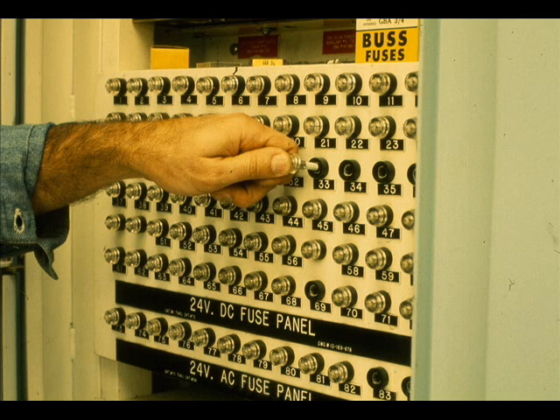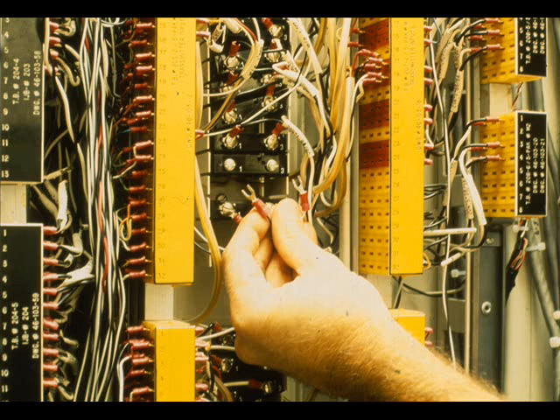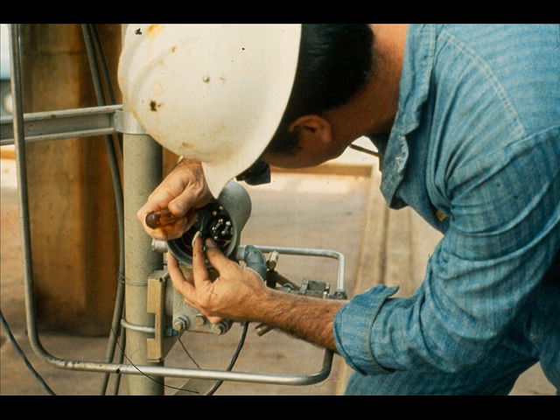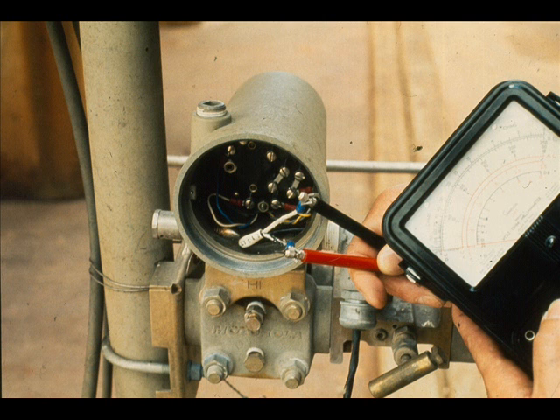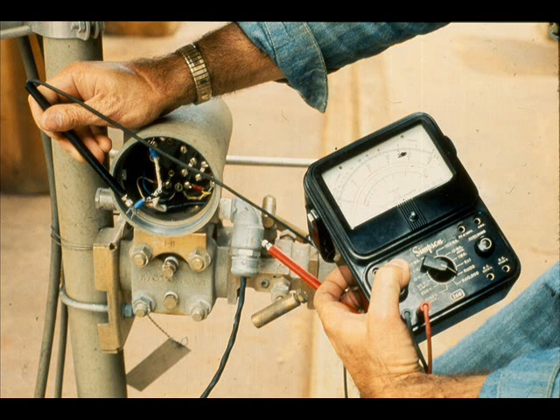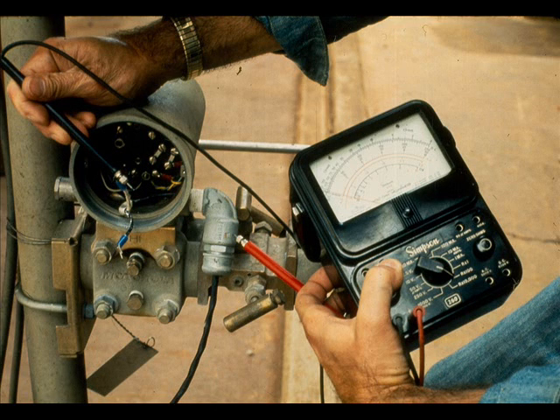To test the signal wires, first remove the DC power from the transmitter loop. Disconnect the signal wires at the control center terminal and at the transmitter. Check the resistance between the two wires. Check the resistance between each wire and ground. All resistance values should be one megaohm or more.